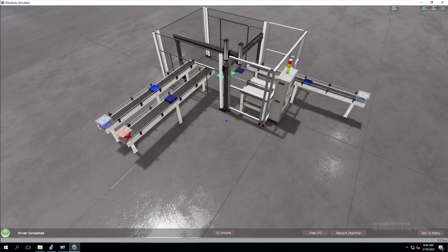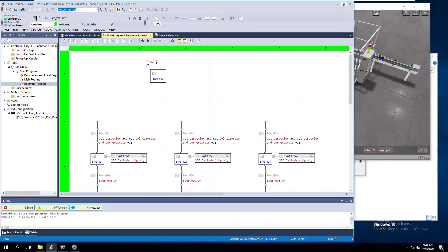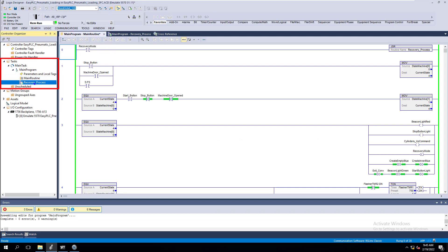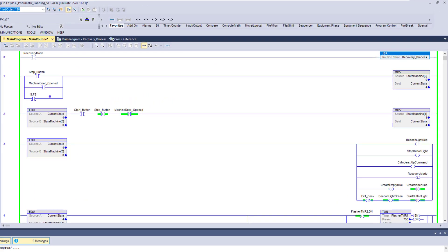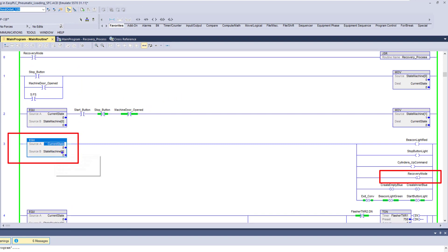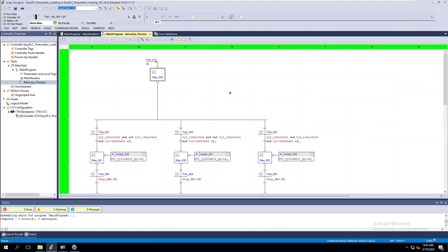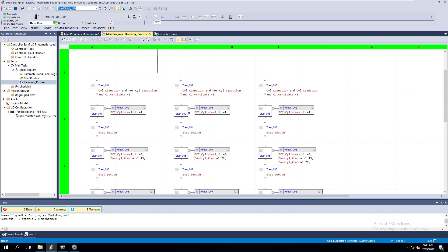You could do a process recovery many different ways. Let me describe exactly how this process works. This process recovery routine right here is not going to be scanned — this JSR is not going to be scanned until it's triggered, until that bit comes high, which means the state machine is equal to zero, which is a safe state. When that's triggered on, that's when the recovery process will actually start scanning. Right now it's not actually scanning at all. It's not going to function in the process.